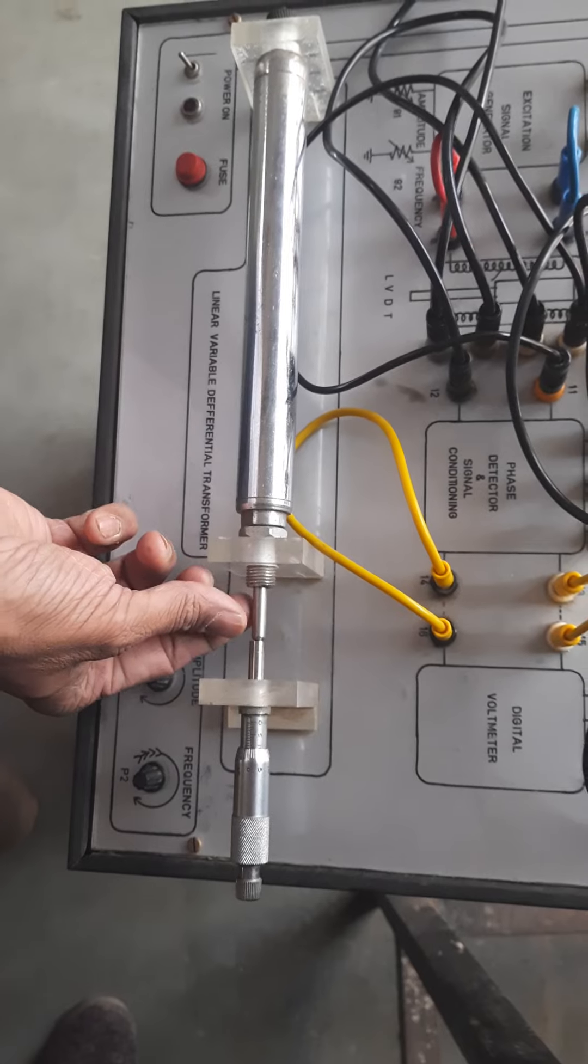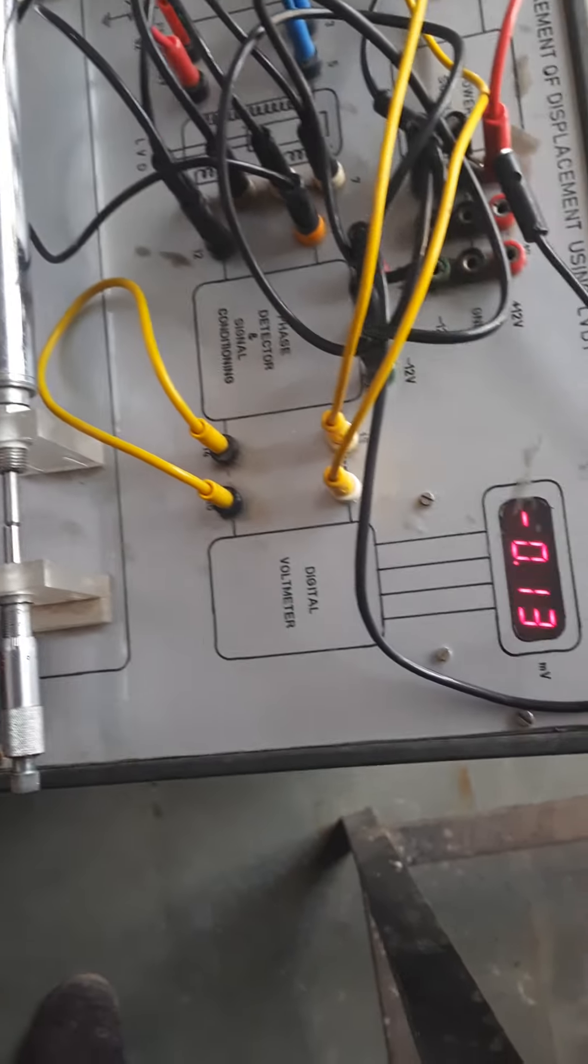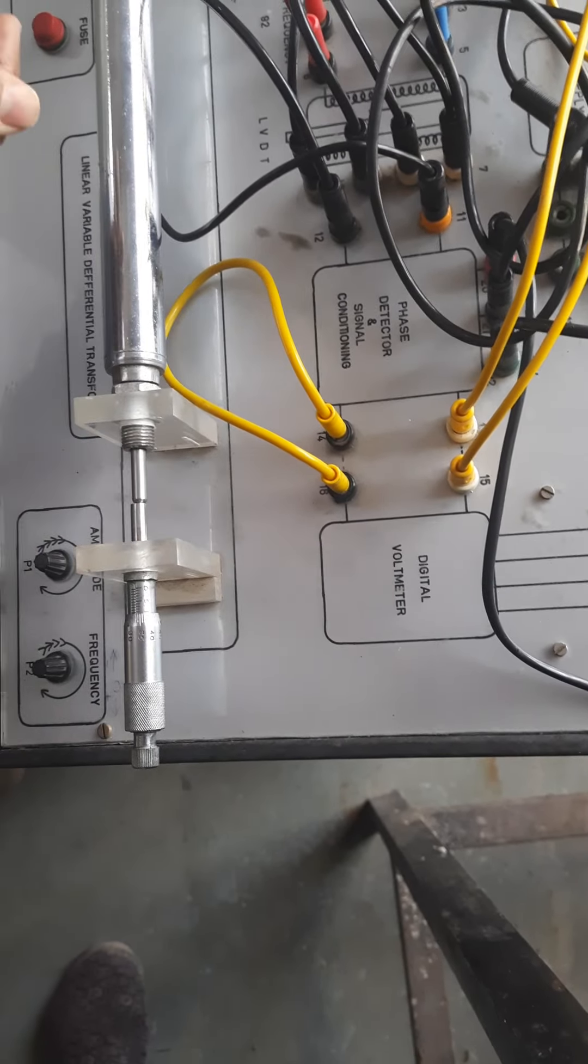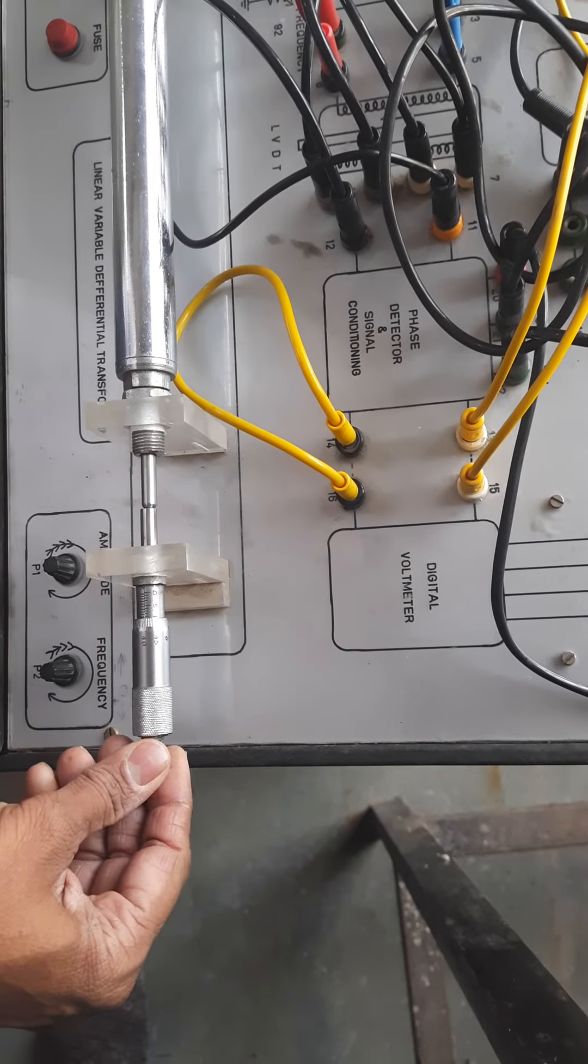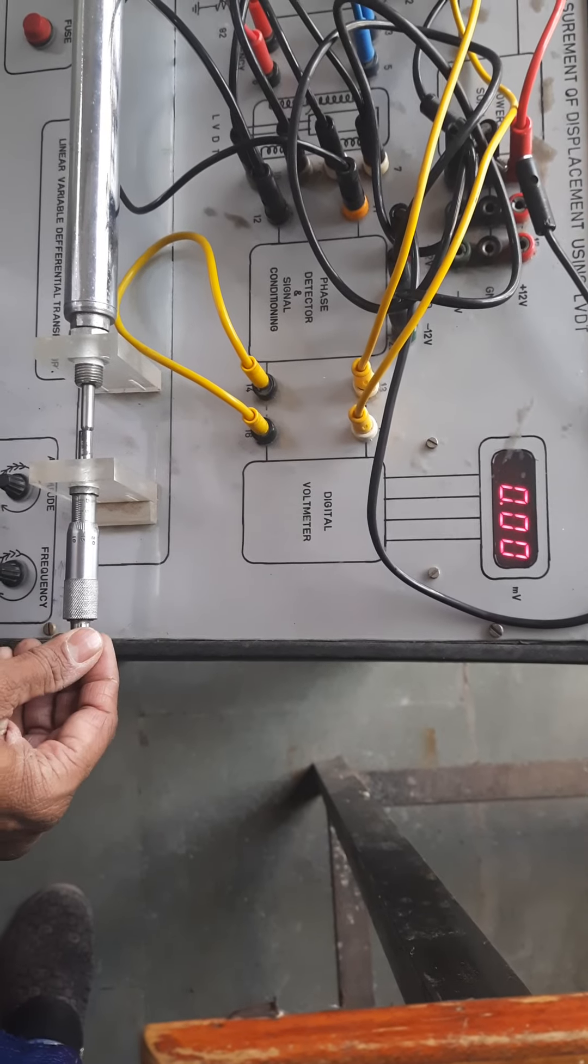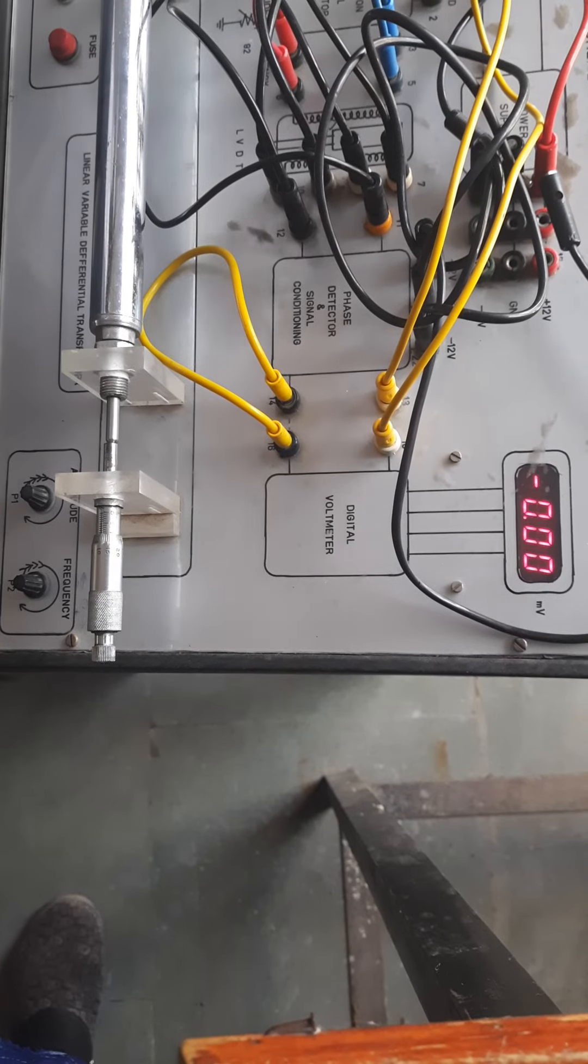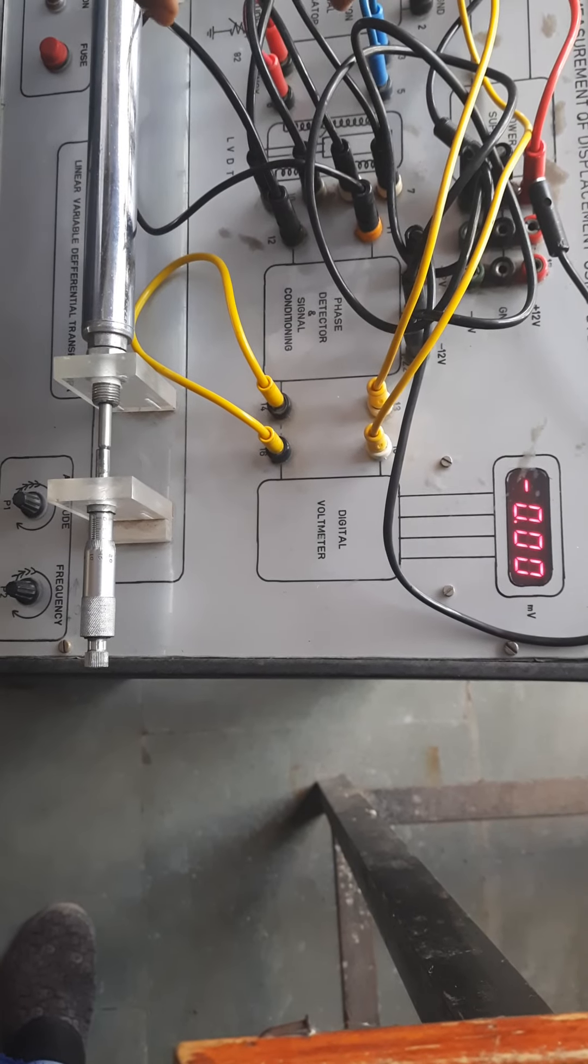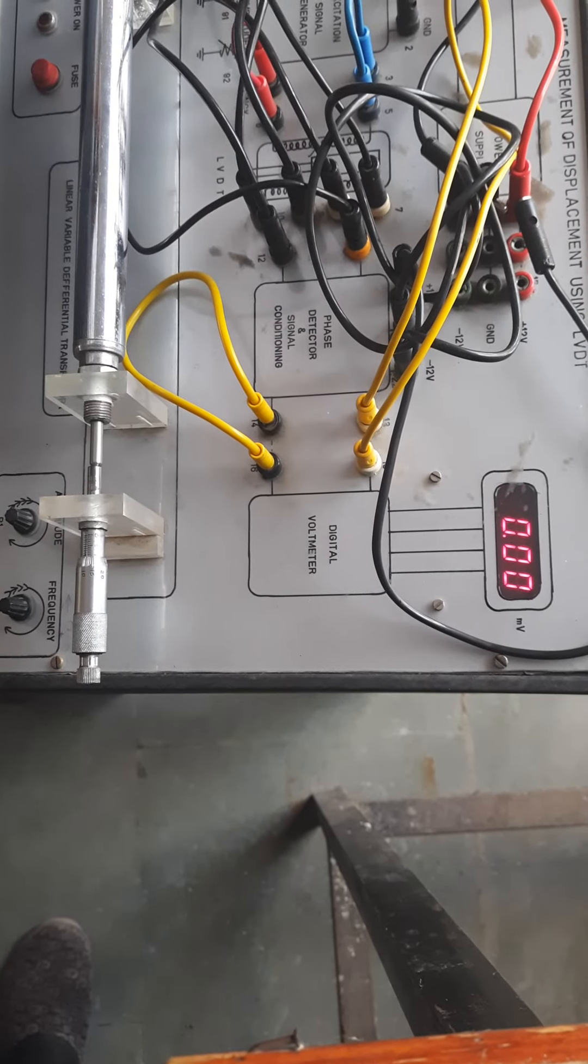Now, look at this section. This is LVDT structure inside. And this is the movable core. Through movement of this, you can change the displacement. You look at, when you press or rotate in clockwise direction, this movable core goes inside. Right. Now, if you want a zero position, null position, I am adjusting and we have checked it is almost near 10 mm, the voltage is zero. So in this case, you can tell that this movable core is at the center so that equal amount of flux will link with both the secondary windings. And both secondary windings are identical in number of turns. So they are generating the same amount of voltage and differential voltage is zero.